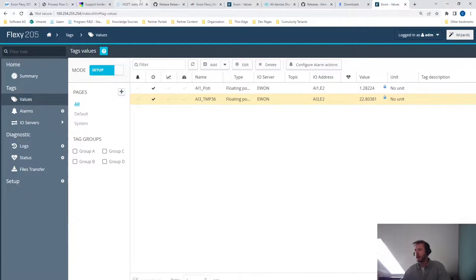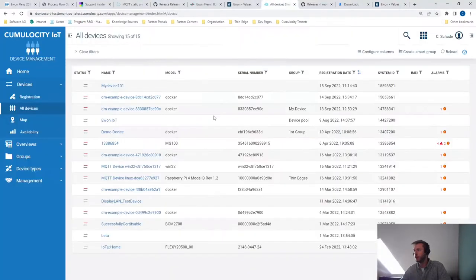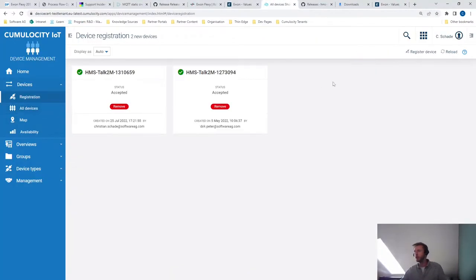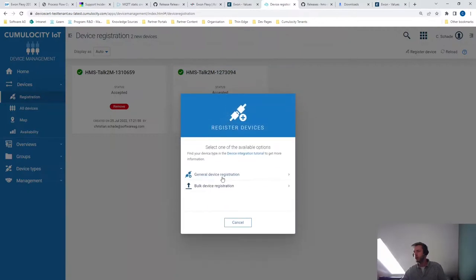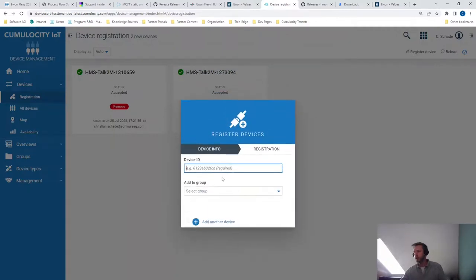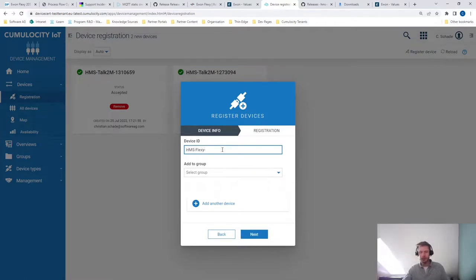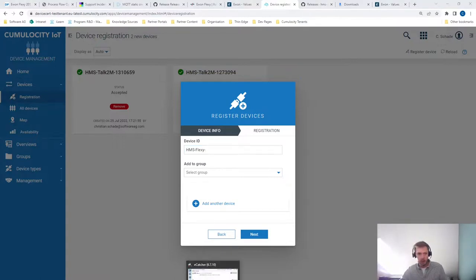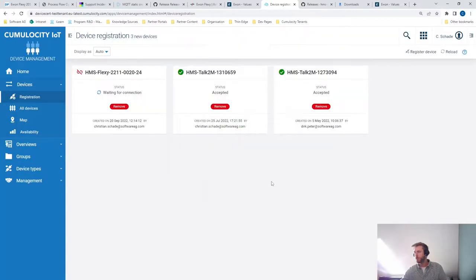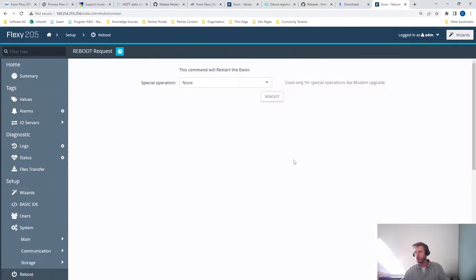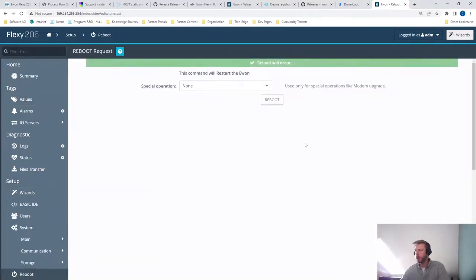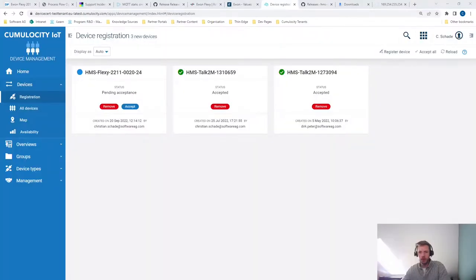And as a next step, you will be entering a registration entry. So this will always be in the same syntax. You enter HMS minus flexy minus the serial number of the device. In my example, this is 2211 minus 24. So this is the registration request. And then we can simply execute a reboot. This will take a while, so I'll be back. You don't need to wait until the device has been rebooted.